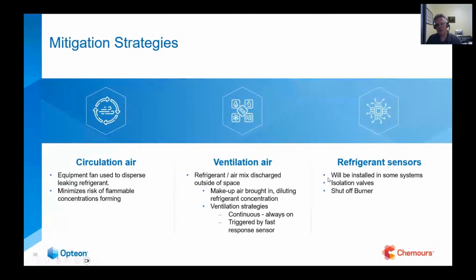So an example would be a ducted home air conditioner. You're likely going to see a leak detector in the A coil. And if that sensor detects a leak that is 25% of the lower flammable limit, so well below the limit which could form a combustible mixture, that sensor is going to send a signal to a board to say, hey, let's shut this unit down, let's shut off the burner, and let's shut off the refrigerant coming into the home. So that's something you're going to see there. The other thing that sensor will likely do is turn on the air handler fan on the residential unit. So it's going to do those three things. But circulation will help ensure that there isn't pooling or a high concentration in one area.